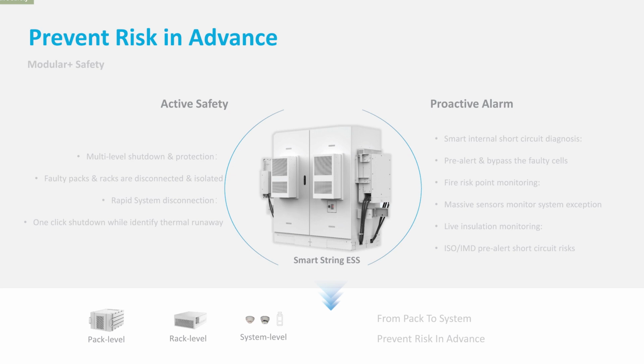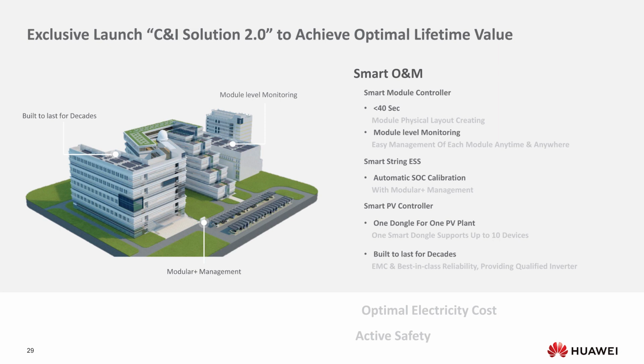We've got proactive alarms, so smart internal short circuit diagnosis. We've got pre-alert and bypass of the faulty cells, fire risk point monitoring, and massive sensors monitoring system exceptions. So we've got temperature sensors, smoke detectors, flood sensors, all of that. And we've got live insulation monitoring. You've got your ISO and IMD pre-alert for short circuit risk as well. We'll go into detail on that.